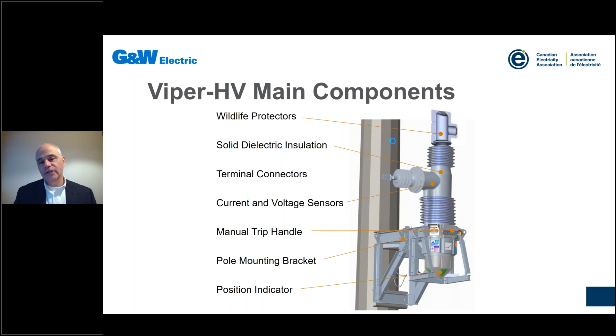As I show you on this particular slide, that side bushing is basically where an integrated bushing current transformer is. And for the very first time in this particular voltage class, we have integrated voltage sensors. The capability of bringing voltage detection down a single cable to the control is super powerful.